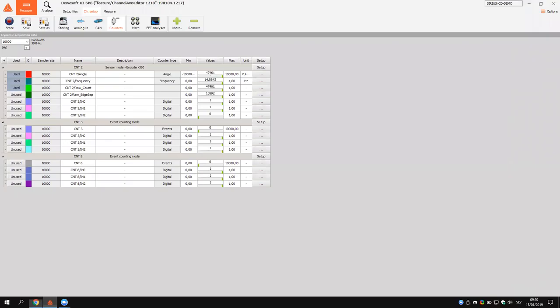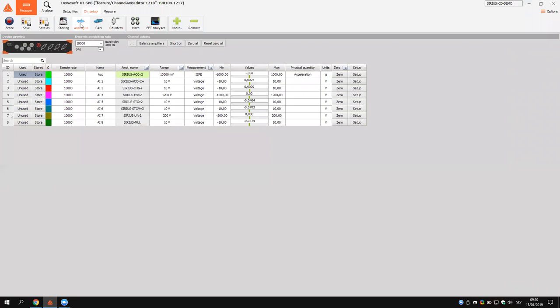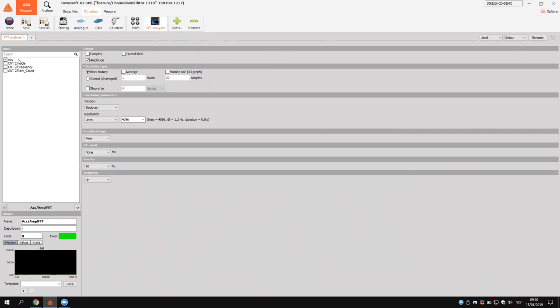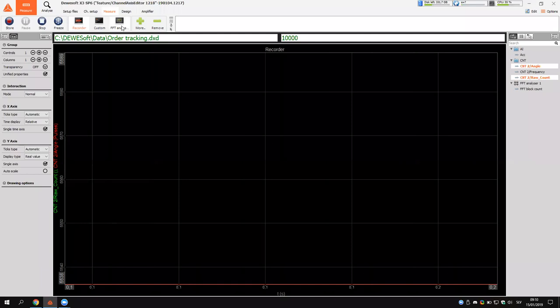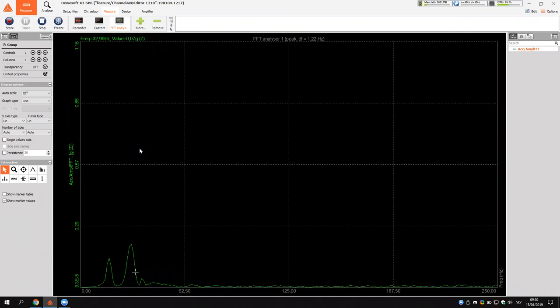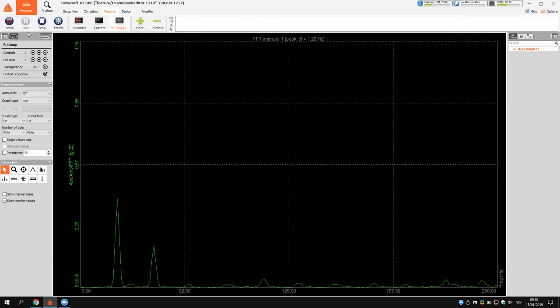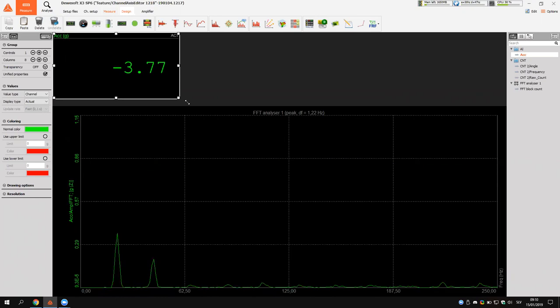Now let's look at why we need order tracking at all. I have the accelerometer connected to my ACC amplifier, and I'll add a simple FFT analyzer. The input will be my vibration channel with a simple FFT with a resolution of 1.2 Hz. When I go to measure mode and run the machine, I can observe the frequency spectrum of my vibrations. In addition, I'll also display the RPMs of the machine, which are measured with the encoder.